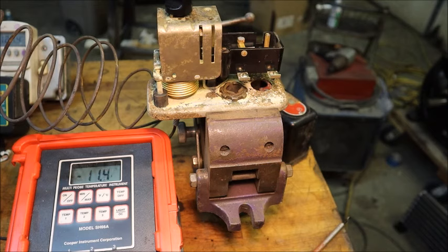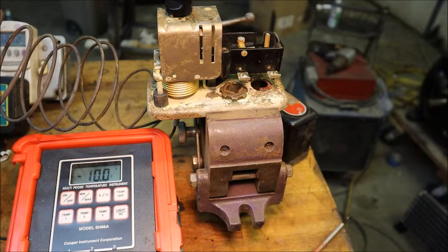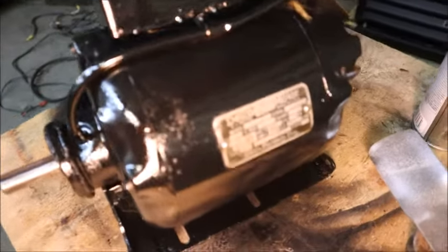Unfortunately I'm out of time for today — got some other obligations. This will take probably another 20 minutes to warm back up and cycle off, or at least warm up to around 32 degrees at our set point where I can work with it, and I'm going to pick back up tomorrow. The control does function but it's badly out of calibration; I'm going to try to get it dialed in and have this part ready to go back on the system.